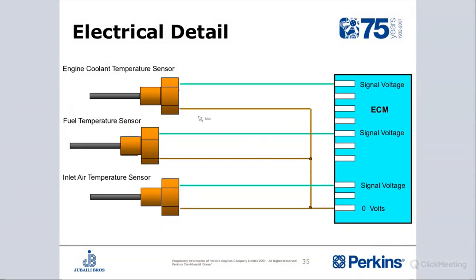The temperature reading sensors, we have three as well: engine coolant temperature sensor, fuel temperature sensor, and inlet air temperature sensor. Two wires again, the signal at 5 volts DC, and the returning signal, which should be between 0.5 and 4.5 volts DC as well. If this sensor gets faulty, your engine will shut down. If this one gets faulty, you will only have a warning.